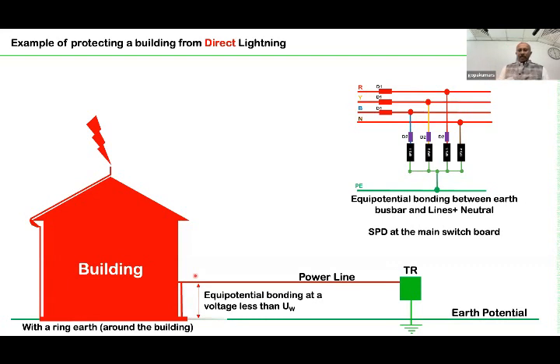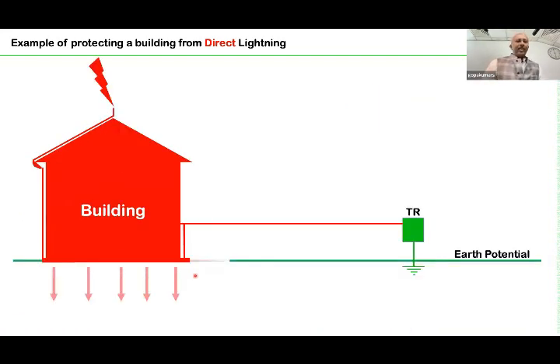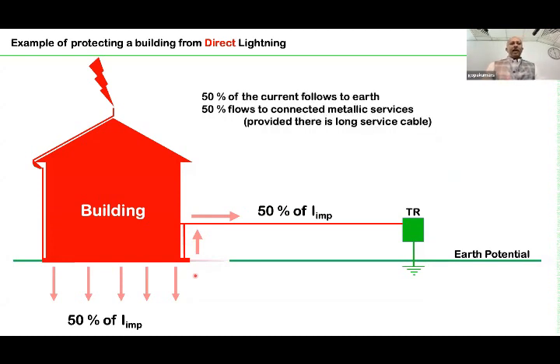One method, one principle which is explained in the standard, is 50-50. Out of the total lightning current, 50% gets dissipated into the earth of the building, and approximately 50% gets diverted to the connected services. Connected services in the sense, probably a metal water pipe, a metal gas pipe, then your power supply and so on. Most of the time, metal water pipe and metal gas pipe are not existing. We have only the power line which is coming from the utility or the distribution company. So approximately 50% of the total lightning current gets diverted to the line.